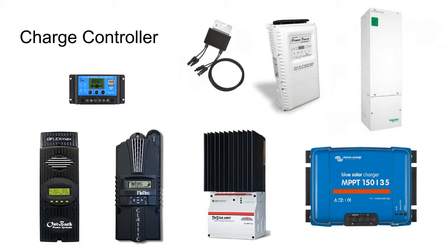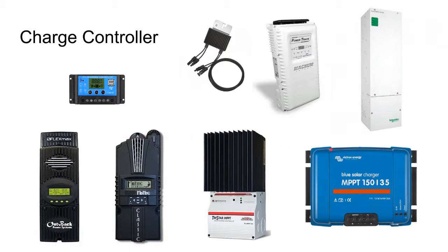So the point is, a lot of these charge controllers — I think Outback has now gone up to 300 volts instead of 150. But if you're looking for a true 600 volt charge controller to limit your circuit number and improve the efficiency of your install, you're really going to choose between Morningstar and Schneider. I like Schneider, it's kind of a coin flip. I don't have enough technical knowledge to speak to Morningstar, although they were highly recommended alongside Schneider by the distributors I looked at.